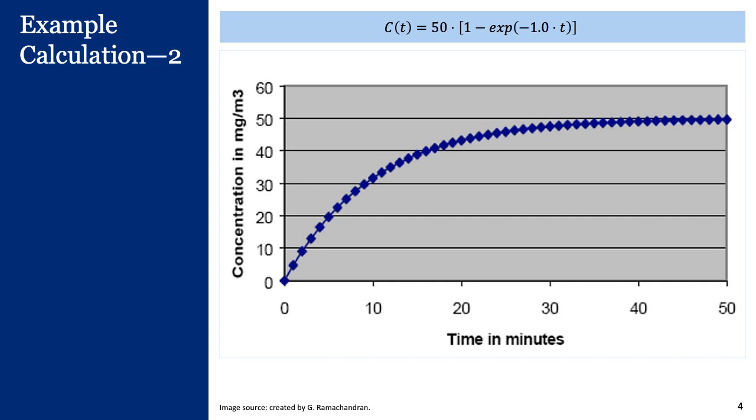And you can see that in the beginning part of the curve. So there is a steep increase. Air is still moving, so there is clean supply air, which is now also cleaning the room, but there is not that much contaminant in the room to be cleaned out. And so the increase in concentration is mainly being driven by the generation process.